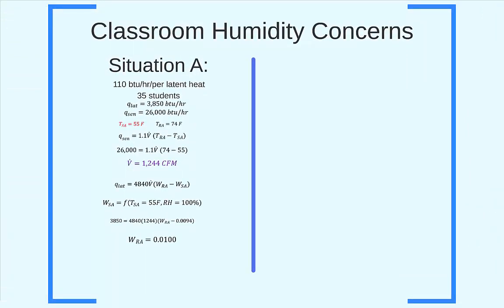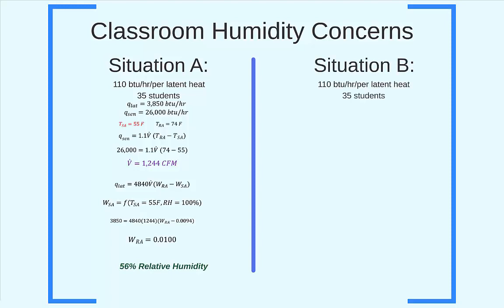Now let's imagine that the majority of the building is empty, and this lack of internal heat gains has resulted in a drop in return air temperature. The reset schedule will then impose a higher supply air temperature set point. But our space is still occupied. The latent load is the same, at 3,850 BTUs per hour, and the sensible load is slightly reduced, but it's still about 20,000 BTUs per hour.